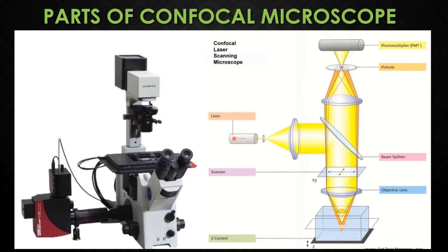The eyepieces are used to view the images produced by the confocal microscope. The pinhole is a type of adjustable aperture that allows the exclusion of most out-of-focus light from the acquired image, thus providing optical sectioning capacity. The size of the pinhole can be set using software on the user's computer. The final part is the photomultiplier tube, or PMT, which converts photons into an electric signal used by the computer to create an image of the specimen.